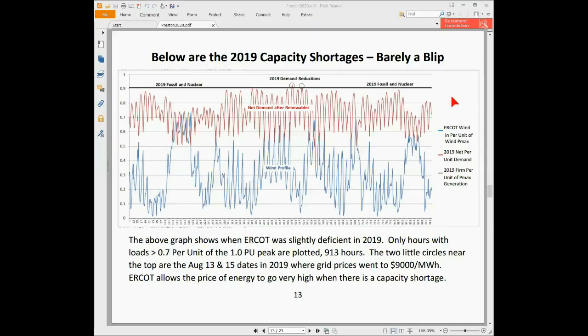I meant to say in that previous slide, we have not added the transportation load yet. Here's a graph of what that 2019 year looks like. I'm only going to graph the load levels for loads greater than 70% of the peak. The 1 right here represents a peak demand of 1 per unit. The reason why the load doesn't go up to 1 per unit is because we're subtracting wind and solar every hour from the native load.